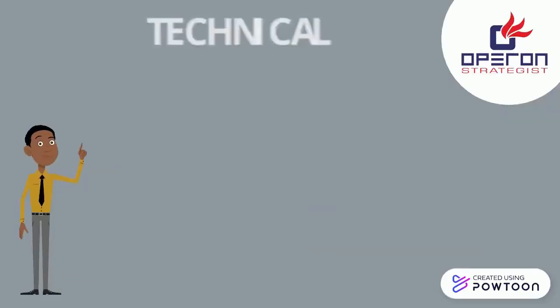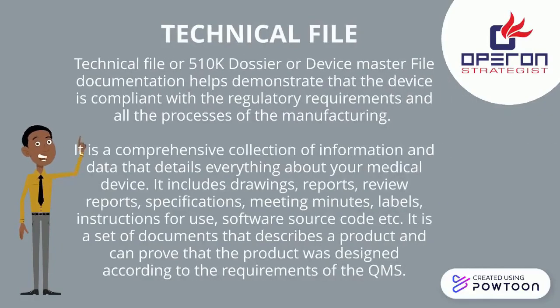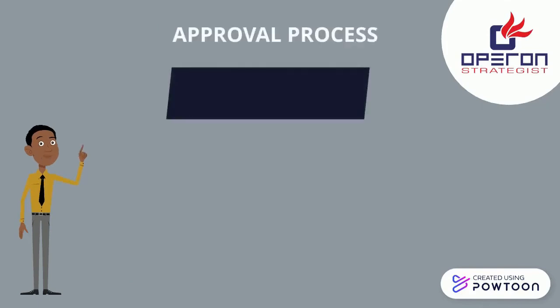It helps manufacturers to build and follow quality systems to help assure that their products consistently meet applicable requirements and specifications. Technical file. Technical file or 510K dossier or device master file documentation helps demonstrate that the device is compliant with the regulatory requirements and all the processes of the manufacturing. It is a comprehensive collection of information and data that details everything about your medical device. It includes drawings, reports, review reports, specifications, meeting minutes, labels, instructions for use, software source code etc. It is a set of documents that describes a product and can prove that the product was designed according to the requirements of the QMS.